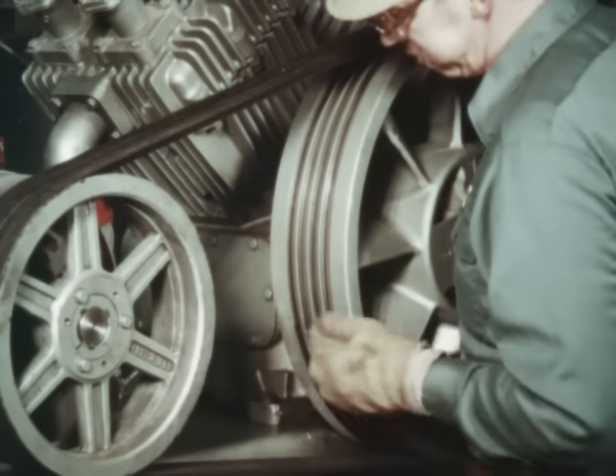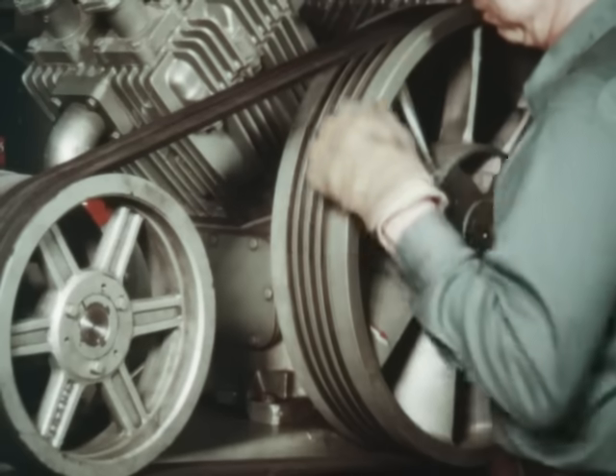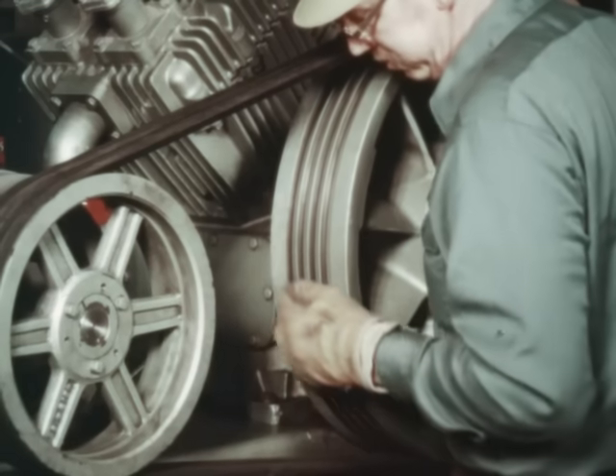Inspect the sheave grooves for any foreign materials. Materials lodged in the sheaves will force the belts from their path in the grooves, causing them to turn over. This problem is resolved by cleaning the sheaves.